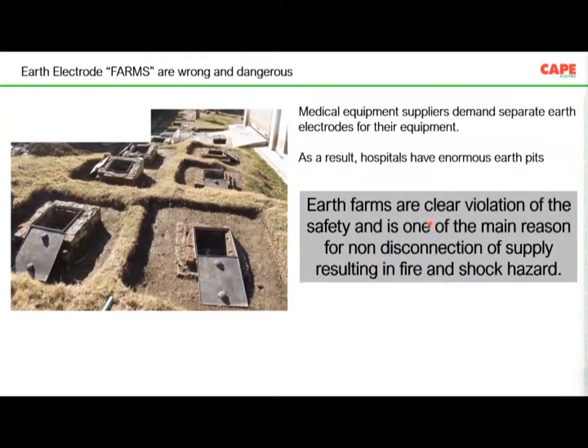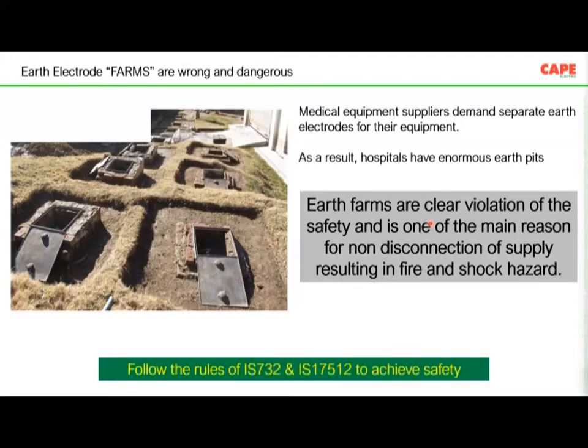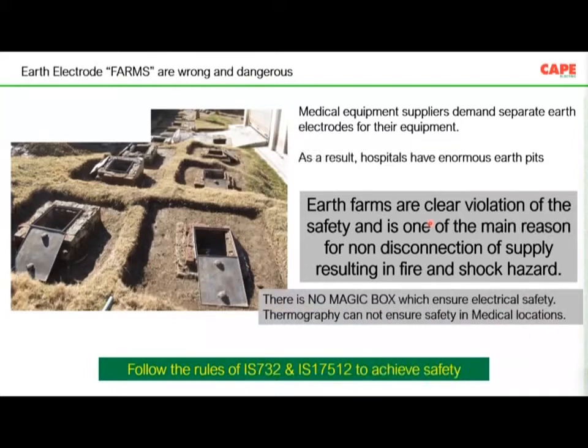So earth farms are a clear violation of safety, and it is one of the main reasons for non-disconnection of supply, resulting in fire and shock hazard. Please don't make it. Also, what you should do is clearly follow the rules of IS 732 and IS 17512 to achieve safety. Also, don't believe in magic boxes. There is no magic box which can ensure electrical safety.